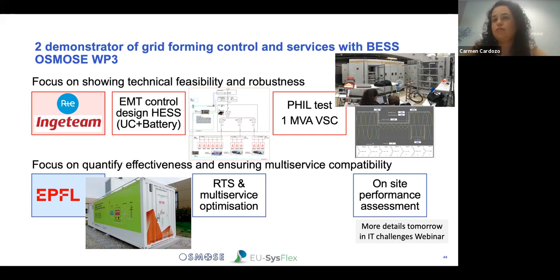test in this demonstrator. In the picture, you see 5 cabinets. This is the full converter with the DC-DC converters, the AC-DC grid forming converter, the filters, the DC side, everything. It's the real power device. And on the right-hand side, you see in black 2 racks, but this is ultra caps. So we put behind the DC bus real ultra caps racks and battery racks. We test the system at reduced power because of the grid emulator that we use. We could not test at 1 MVA, so we tested about 100 kVA. And the grid emulator could perform many things like phase jump, unbalanced fault, inject harmonics, and anything that we wanted.